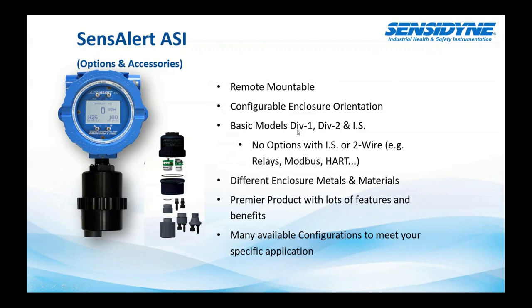Basic models for Class 1, Div 1, and Div 2, and IS. Different enclosure materials. We can do this in stainless if we need to. Don't see that a whole lot in water wastewater, but it is available. Stainless steel sensor housings, stainless steel transmitter housings, or even PVC in different plastics. Like I said, lots of features and benefits in different configurations we can get into with this.